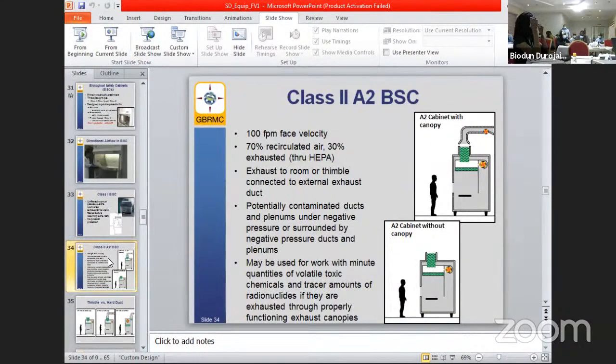I remember I was consulting for a laboratory in Lagos at the middle of the pandemic, and the biosafety cabinet was 2 months due for recertification. We were doing a lot of engineering for new reconstruction to make sure that the laboratory is fit for COVID assay. Now, this is what I did. The filter is supposed to be trapping in here. So I went in there, put some papers on nylon, expecting that it should trap. It's not trapping. Something is wrong.